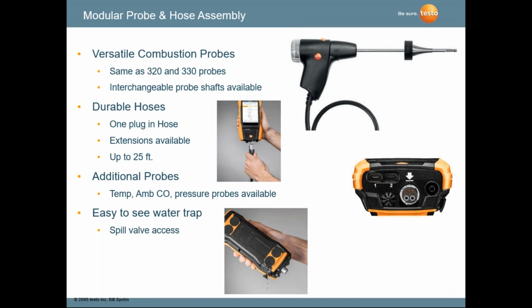Again, I can't speak highly enough about Testo's probe and hose assembly. If you've used a Testo probe and hose assembly before, I think you'll agree it's very rugged, very modular, very adaptable to different stacks, because you can take the probe tube off at the probe handle and replace it with a longer probe, a flexible probe, or a high temperature probe. We get involved in a lot of different applications, from a residential boiler to large utility boilers. Additional probes, water trap is at the base of the instrument, spill valve access.